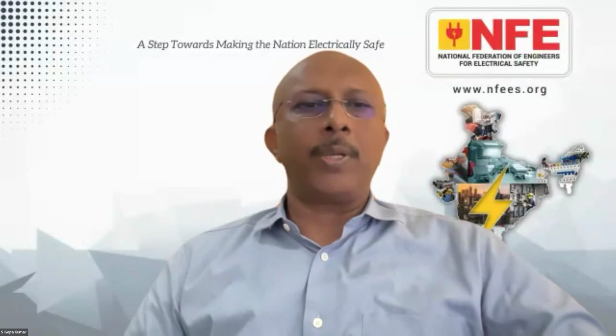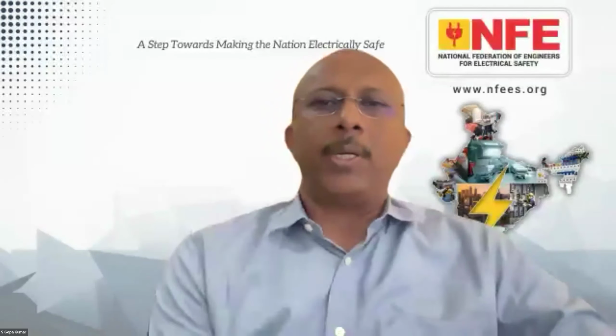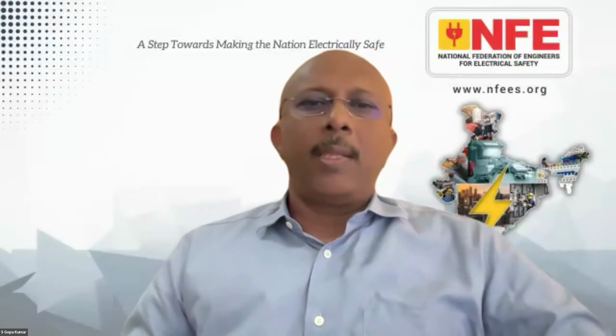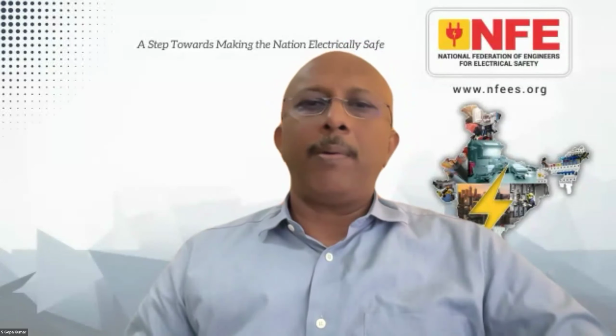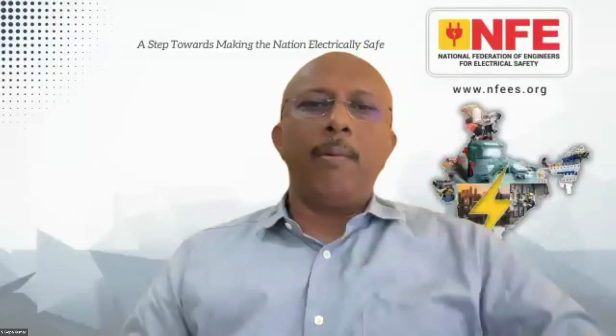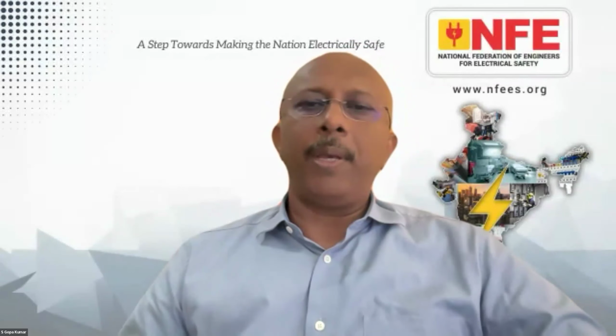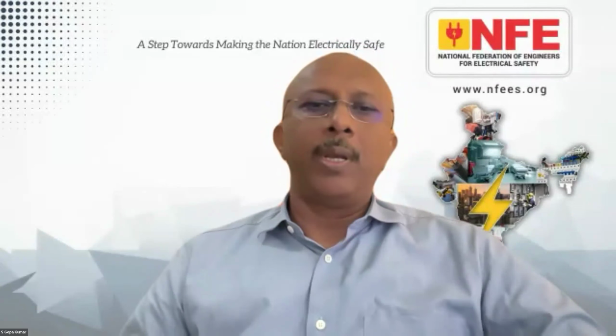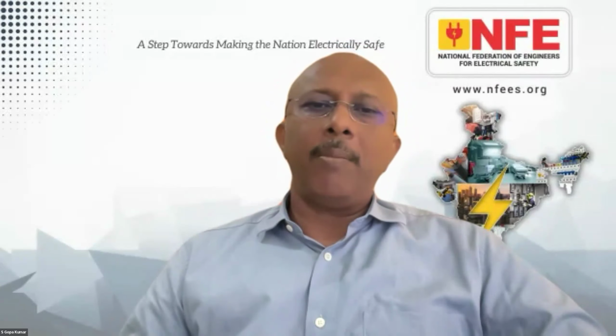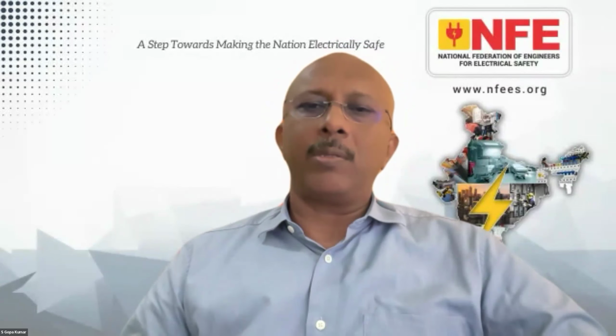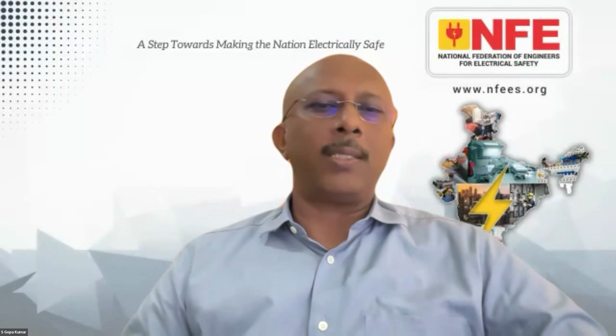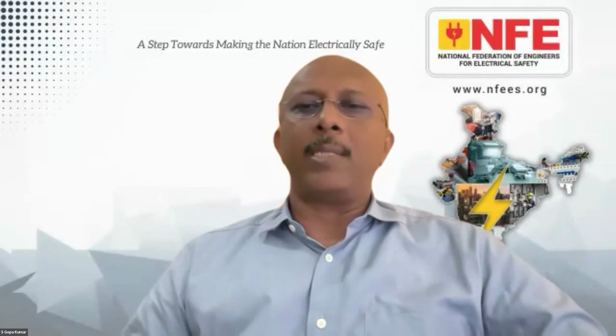So there is, because open circuit voltage and short circuit current are also measured, so it will trip. Then the second question from Mr. Albert Shager: our building has a three-phase connection having 5 distribution boards, including TPN and single-phase SPN DBs. Should each place a 30 milliampere RCCB, or can I fix one only in the main panel? That means, can I fix one RCCB at the main panel, or should I fix an RCCB in each panel? Krish, probably you can answer this.